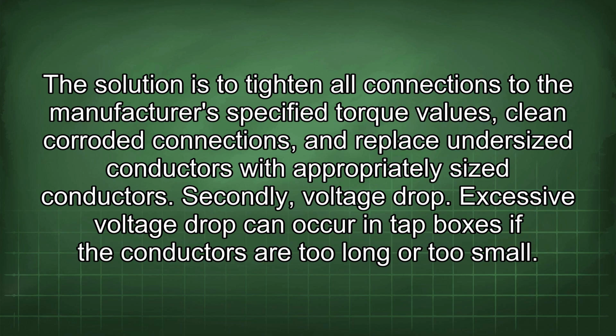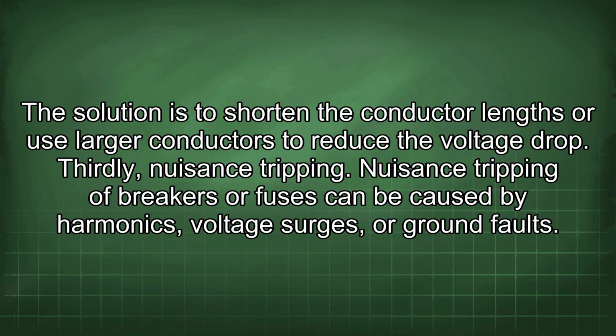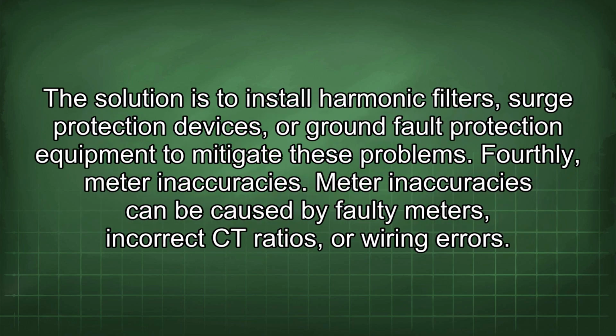Secondly, voltage drop. Excessive voltage drop can occur in tap boxes if the conductors are too long or too small. The solution is to shorten the conductor lengths or use larger conductors to reduce the voltage drop. Thirdly, nuisance tripping. Nuisance tripping of breakers or fuses can be caused by harmonics, voltage surges, or ground faults. The solution is to install harmonic filters, surge protection devices, or ground fault protection equipment to mitigate these problems.